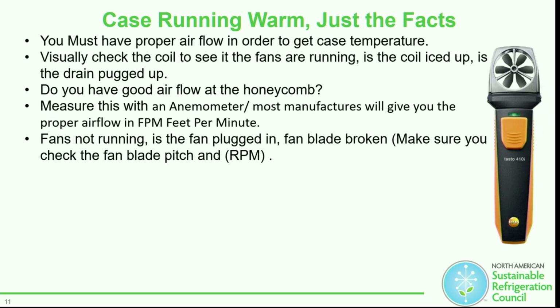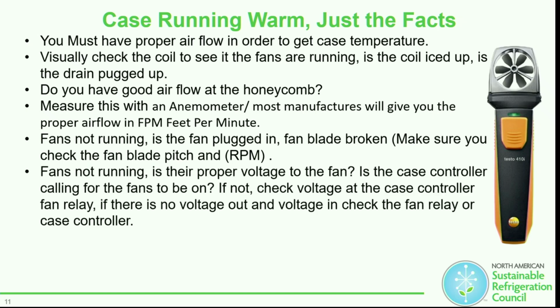When you turn around some of these motors, they have a little hole in the back that looks like a battery cover. There's actually a probe you can put in there to see exactly what RPM the motor is programmed for. Just because it says 1500 doesn't mean it's running 1500. Also, helpful tip: read the instructions and make sure the motor is not plugged in when you push in that little thing, because it hurts things badly. I was like, why wouldn't they put that? Oh, it's on there.